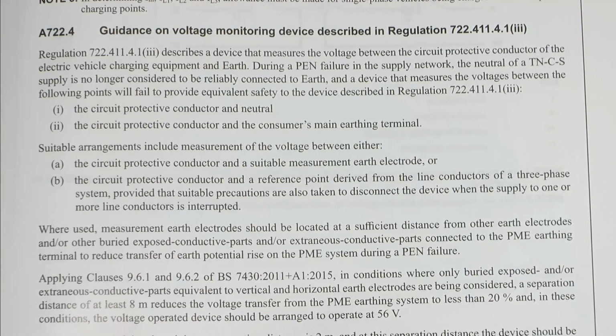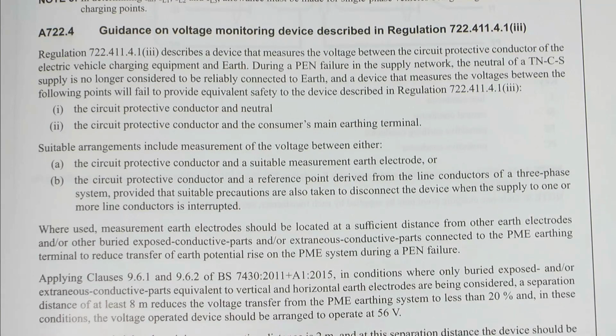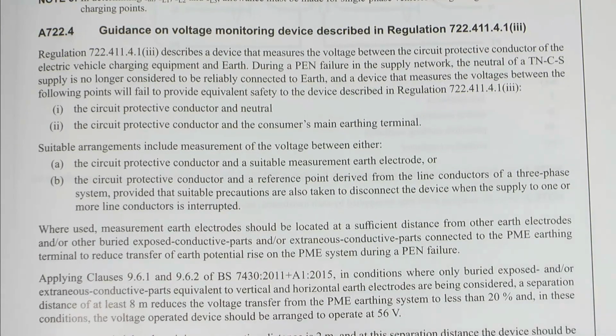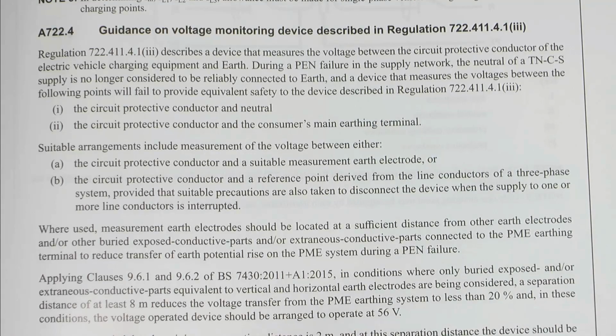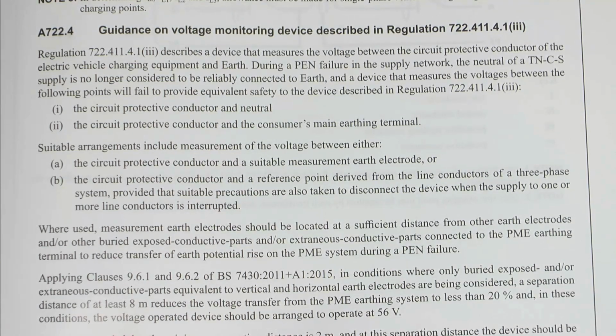Suitable arrangements include measurement of voltage between either the circuit protective conductor and a suitable measurement earth electrode, so that's going to be a separate electrode installed that's only connected to the EVSE, electric vehicle supply equipment, and that will be put into the ground somewhere suitable, and suitable means away from any other parts which may be connected to the main earthing terminal, so metal pipes and cables and all of that.